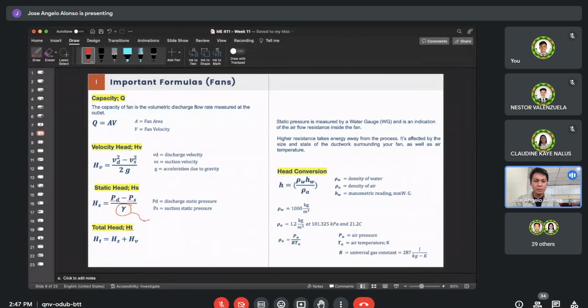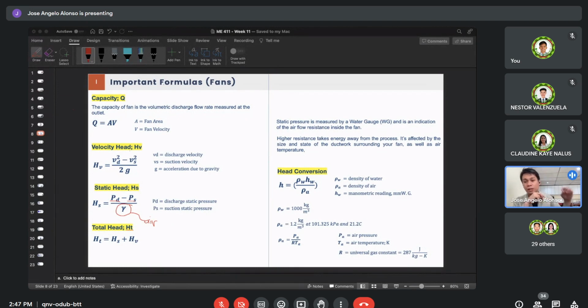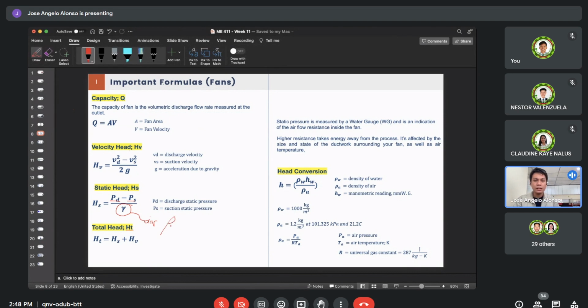We only use 9.81 kN per cubic meter and 62.4 pounds per cubic feet when water is our medium - that's applicable only to pumps and turbines. But when it comes to fans and blowers, we use the specific weight of air, which is the density of air multiplied by acceleration due to gravity.